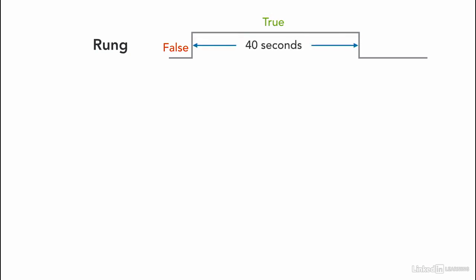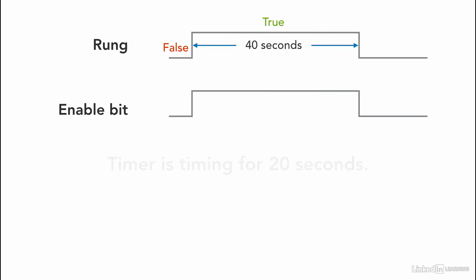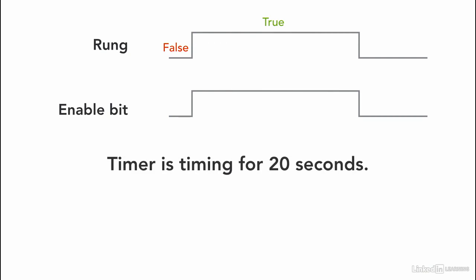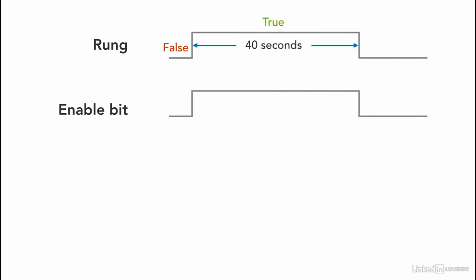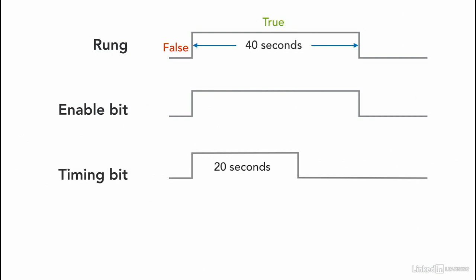Whenever the rung is true the enable bit becomes true as long as the rung is on. The timer is set to time for 20 seconds. So the timer is timing for 20 seconds only. This means the timer timing bit is activated only for 20 seconds. After the 20 seconds the timer timing bit goes to false.